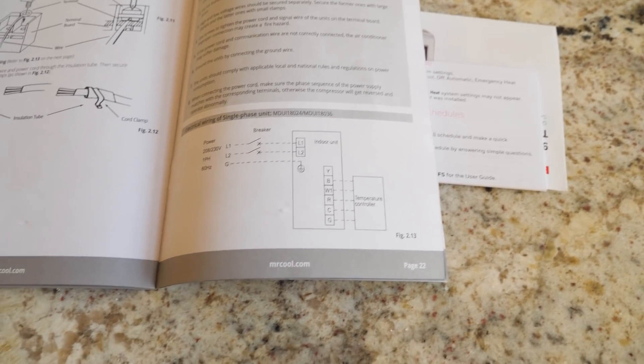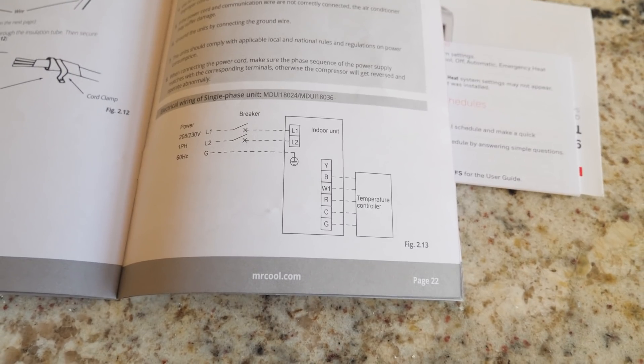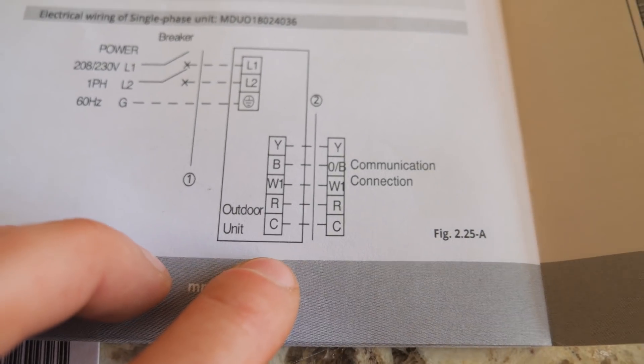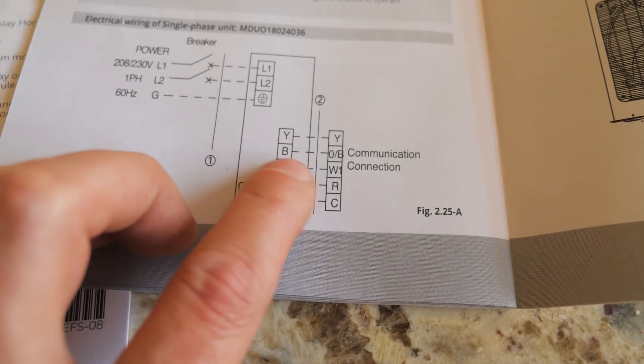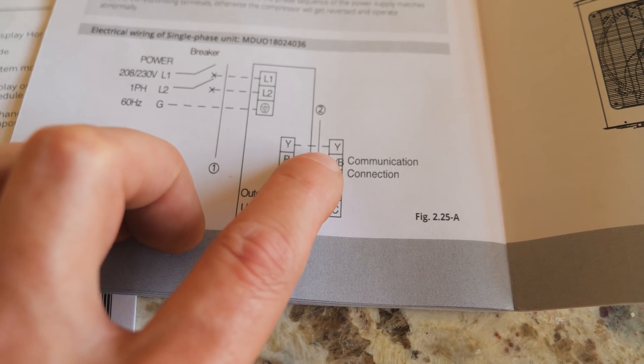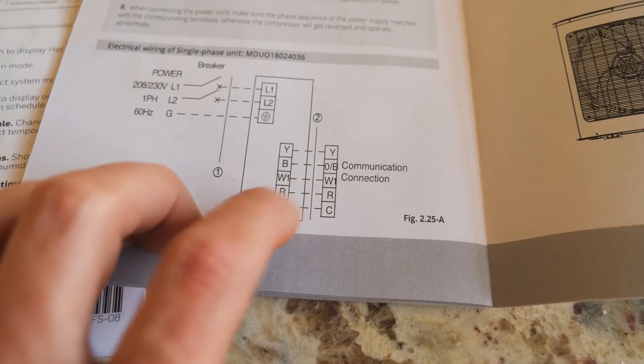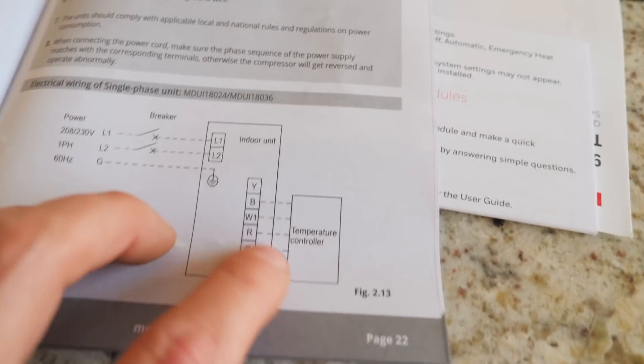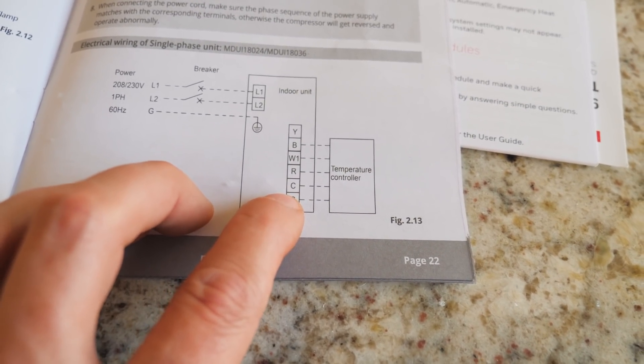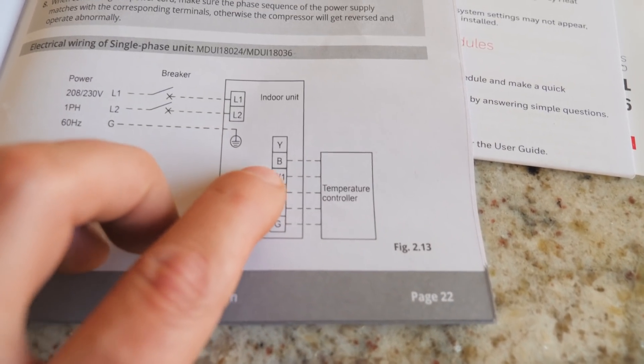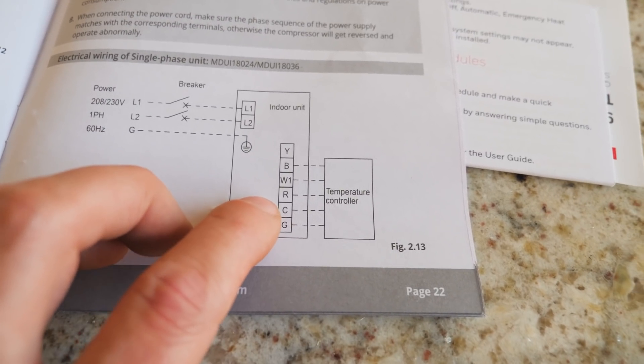So I had a problem and it was my fault but it was actually their fault because their directions are not very clear for someone who's never done this. On the terminals for the communication wire your outdoor unit runs to your indoor unit and here you have a Y which is the compressor contactor and mine has that, it has the yellow wire going to the yellow wire on the air handler.